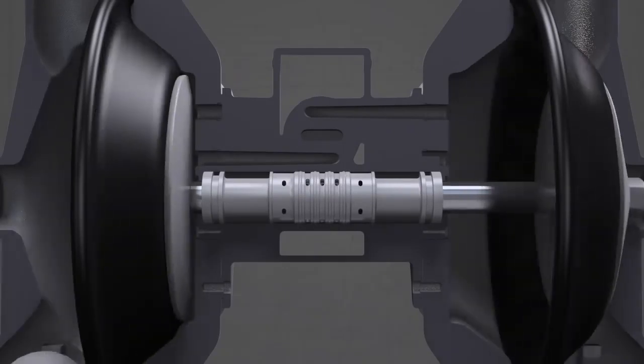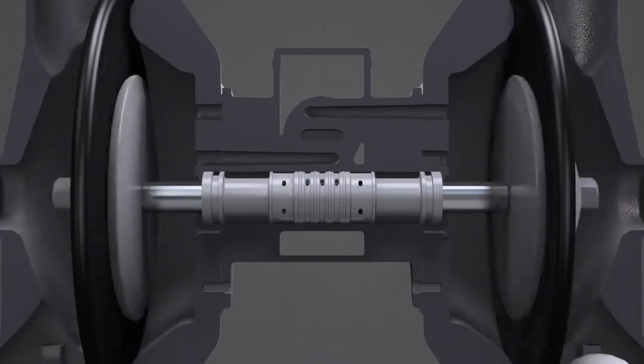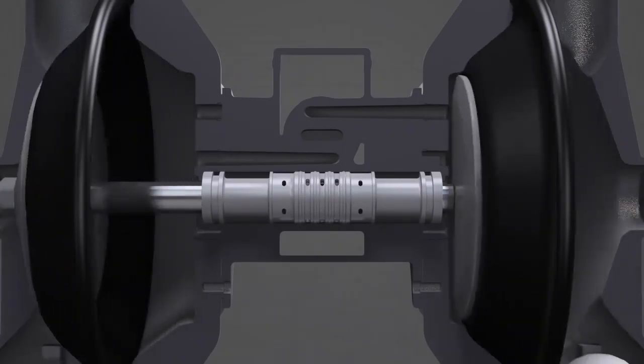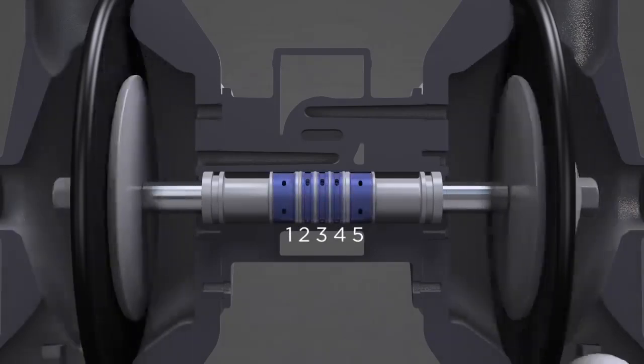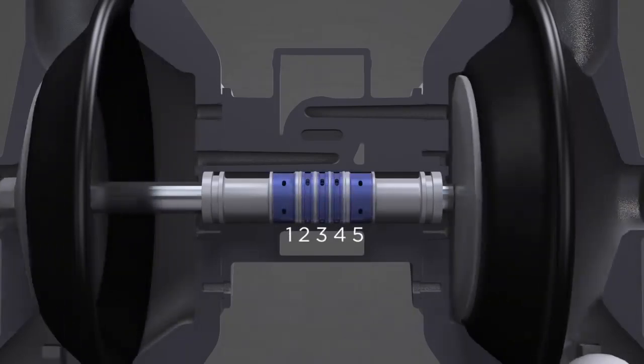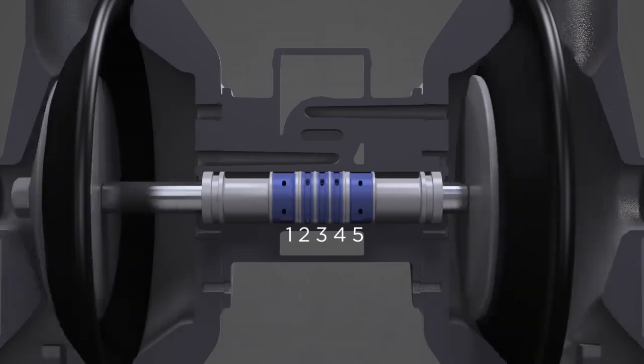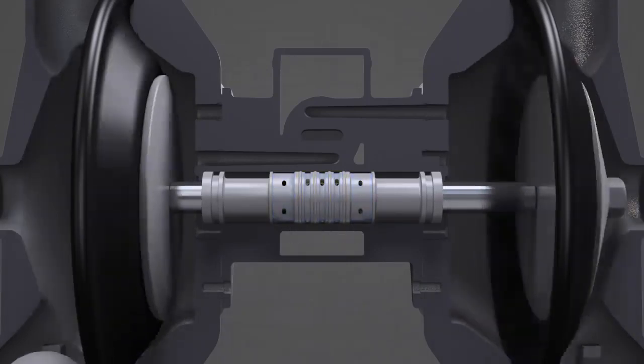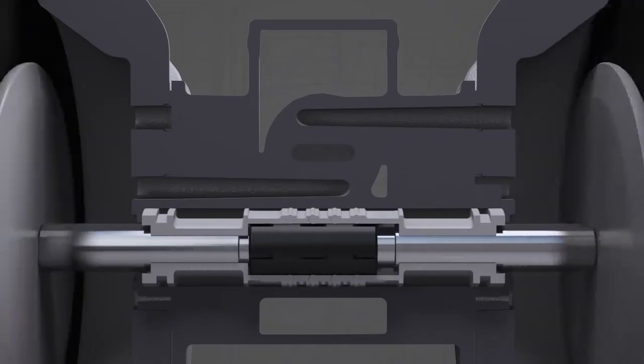The pilot air valve directs the air that moves the main air valve. It is constructed of five separate chambers and a central rod that moves side to side due to the diaphragm pressurizations. The pilot and main air valves work together to drive the pump.